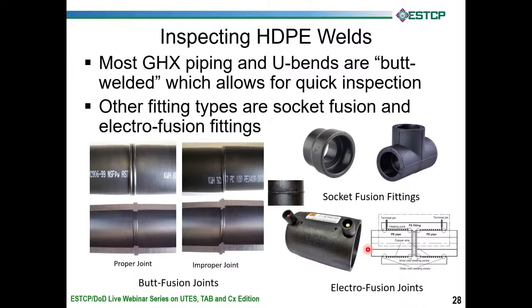But these joints are very expensive, so you don't. They're kind of a specialty thing you see for retrofit and other work, but most geothermal heat pump systems use a butt weld. And the beauty of the butt weld is, as you can see here, you're basically taking a specialized machine and you're heating up the face of one pipe and then the other pipe to get them soft to a certain discrete temperature point. And then you push those two pipes together.